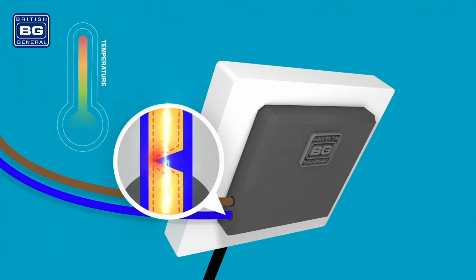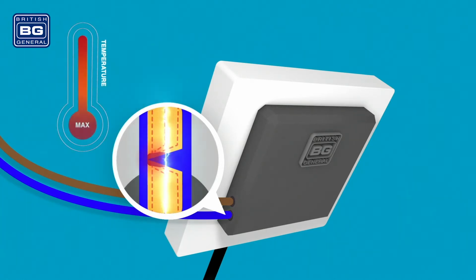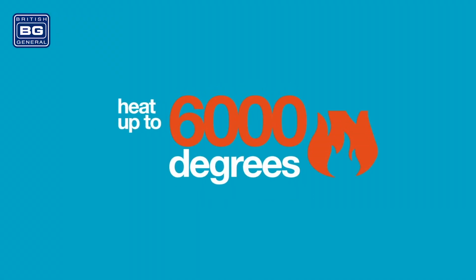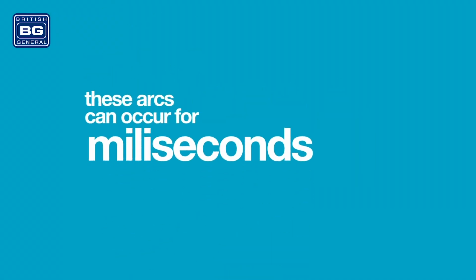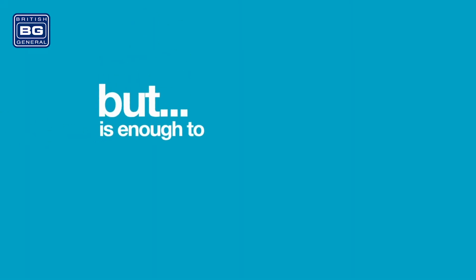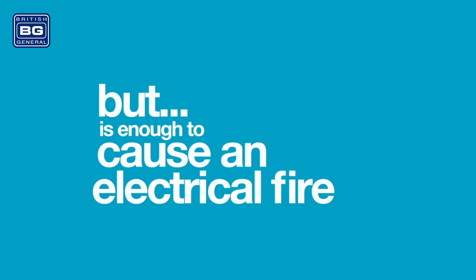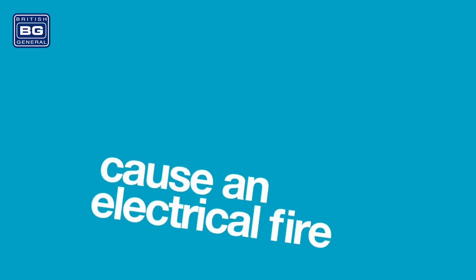Temperatures over 1,250 degrees Celsius can cause the cable's copper and insulation to carbonize. Now this would depend on current flow. This forms an arcing condition where a stable arc can form and heat up to 6,000 degrees Celsius. Now, these arcs can occur for milliseconds, but it is enough to cause an electrical fire. These arcs can occur naturally in homes. Something as simple as trapping cables indoors or crushing cables can cause arcing conditions. Piercing the cable insulation is another common cause.